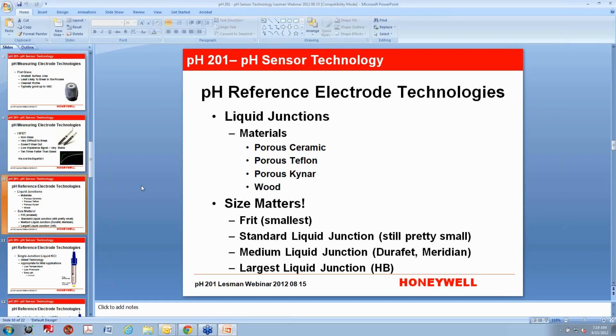So go ahead and head back on to the reference electrode technologies. And the first order is the liquid junctions. Liquid junctions are simply a porous material of some sort. It can be anything from a hole to porous ceramic or Teflon or Kynar or even wood. There's sensors out there that have wood liquid junctions. The liquid junction is really important because it allows electrical contact between the process, the measuring electrode, the process, and the reference electrode, because current has to flow through the sensor for you to get a reading. And if you lose electrical contact, you lose the current, and then you don't get a reading.